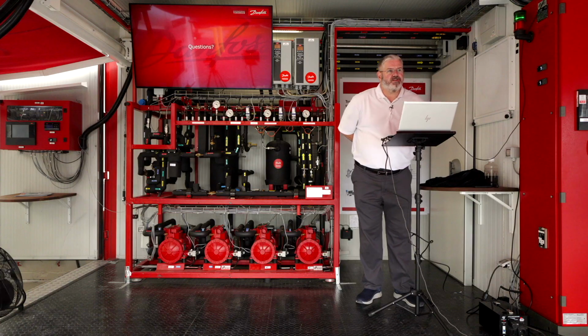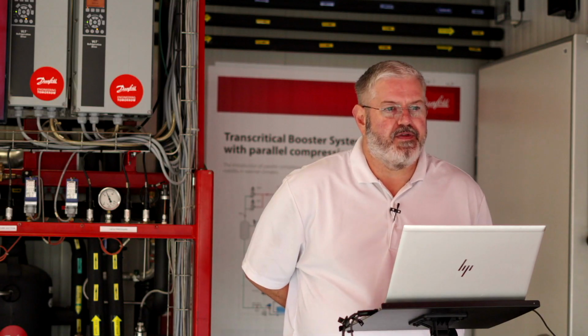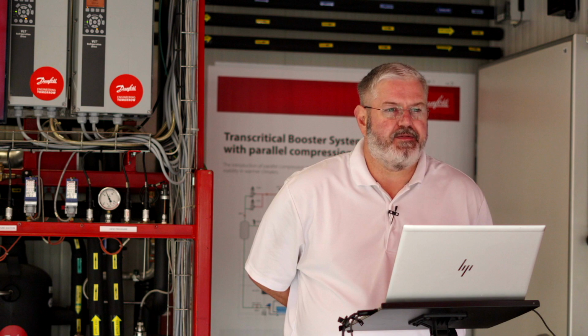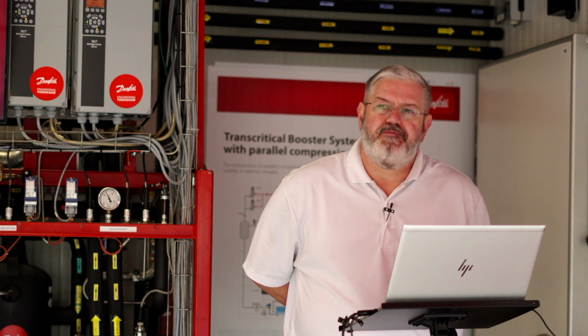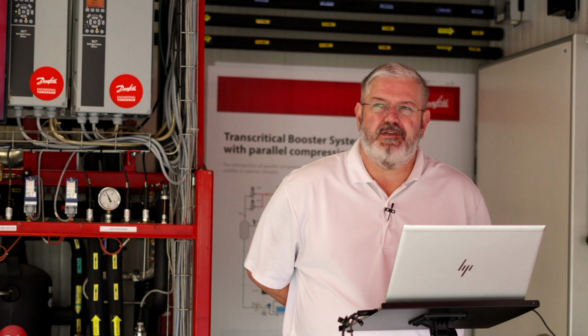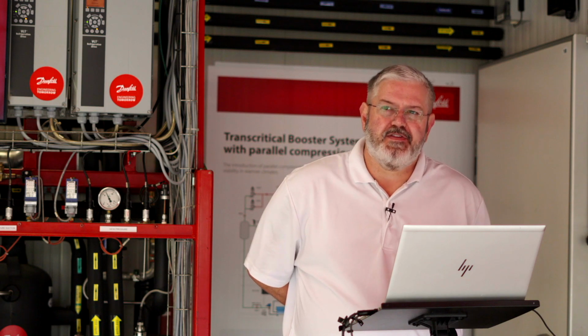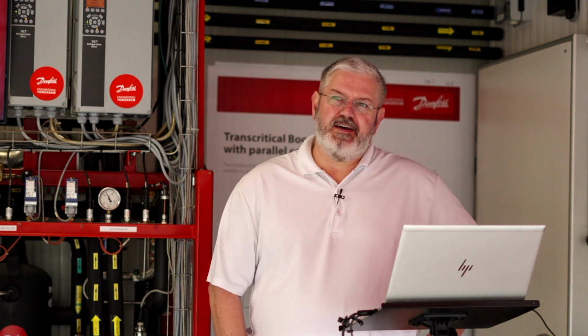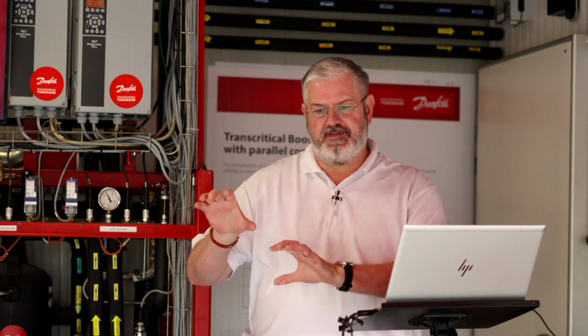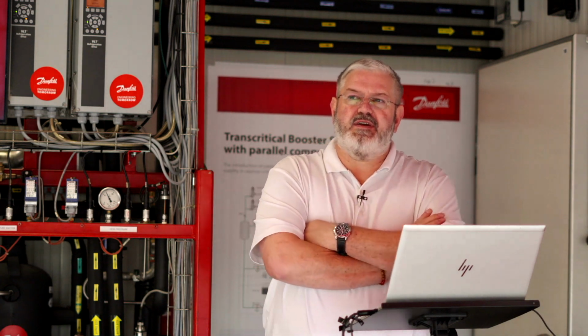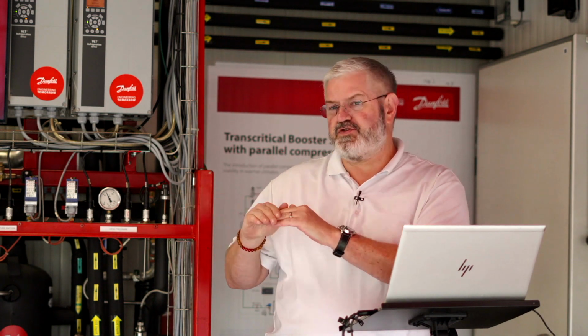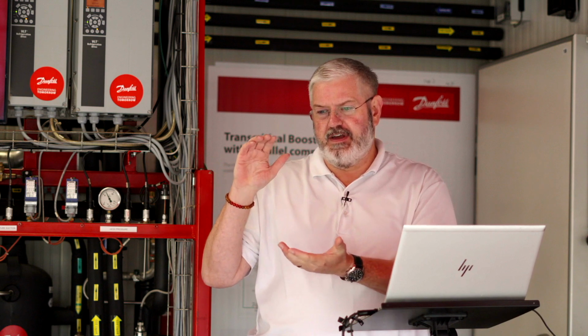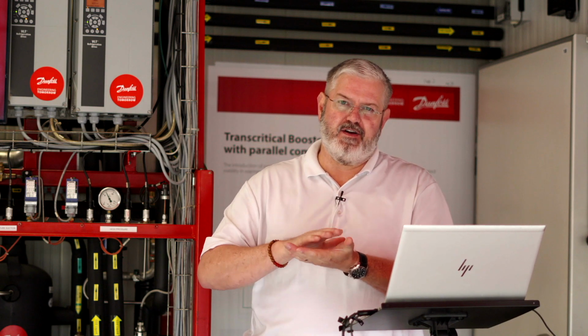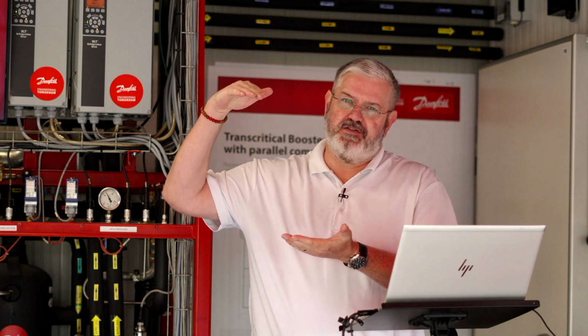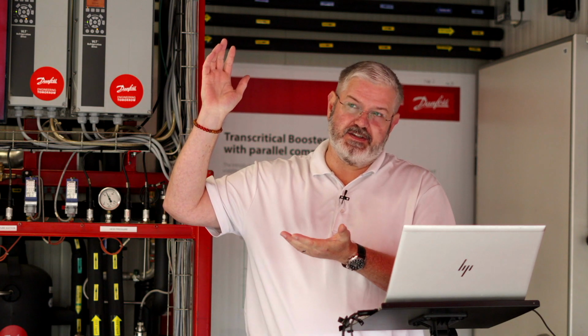So we have another question. What risk of bleed-by is there when both the high pressure valve and ejector block are piped into the system? I mean, bleed-by, I guess that question would determine if you're using the high pressure valve, maybe you're kind of partially feeding one or the other. What really happens is you'll switch from one to the other. Like if you had all the solenoid coils burn out on the ejector block, pressure's going to rise to a certain point and the high pressure valve is going to take over as a safety backup.